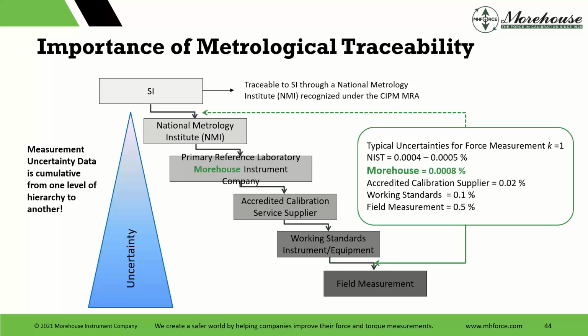Anyway, so how does uncertainty work? Measurement uncertainty data is cumulative from one level to a hierarchy. We're looking at measurement traceability, which Patrick, who's now an assessor with A2LA, should know is an unbroken chain of calibrations, each contributing to the measurement uncertainty.